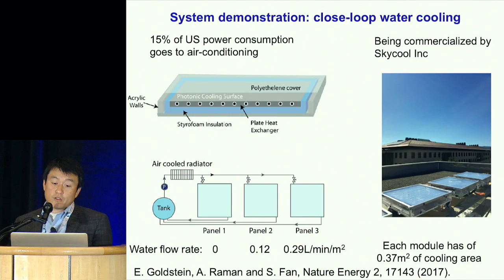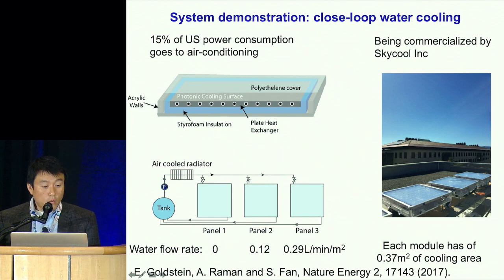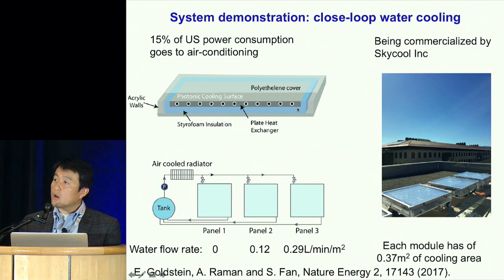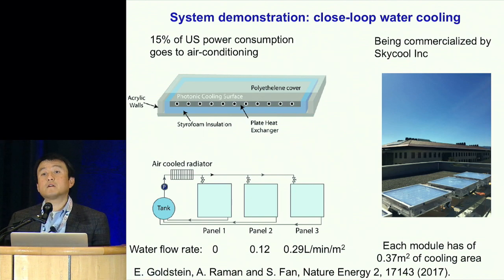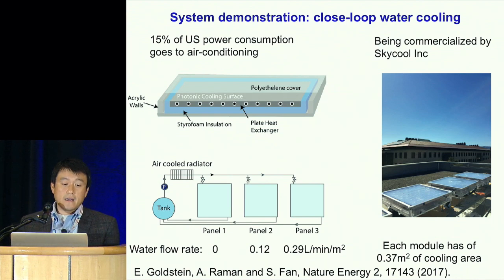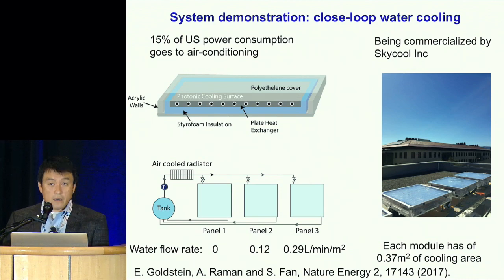This is something we've recently done. We built these panels and modules, and underneath each radiative cooling panel we have a circulating water pipe. This allows us to lower the temperature of the water below ambient air temperature. That water can then be fed as the cold side into a water-cooled cooling tower. We estimate that a few degree reduction in inlet water temperature translates into about 10% efficiency improvement in these water-based air conditioning systems.